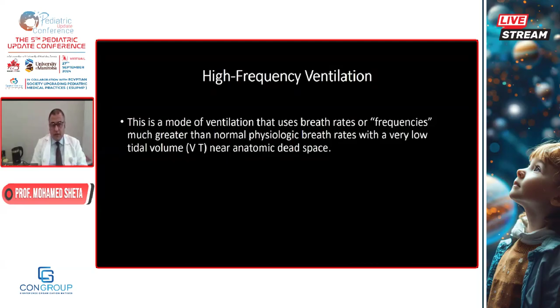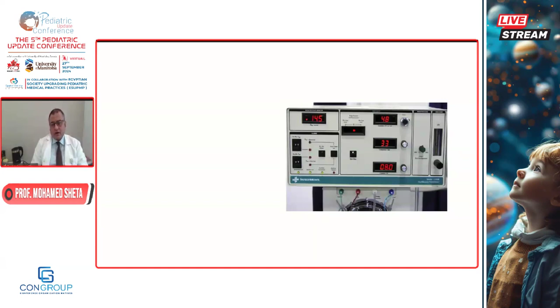High frequency ventilation is a mode of ventilation that uses breath rates or frequencies much greater than the normal physiological breath rate with a very low tidal volume. So it's less traumatic than conventional ventilation. Always remember that high frequency is less traumatic for the lung tissue than conventional ventilation because it uses a tidal volume near the anatomic dead space. This is a picture of the SensorMedics, which is one of the common high frequency ventilators, and we will talk about high frequency ventilation generally, just to give a note for our colleagues if anybody encounters high frequency elsewhere where you are working or practicing.